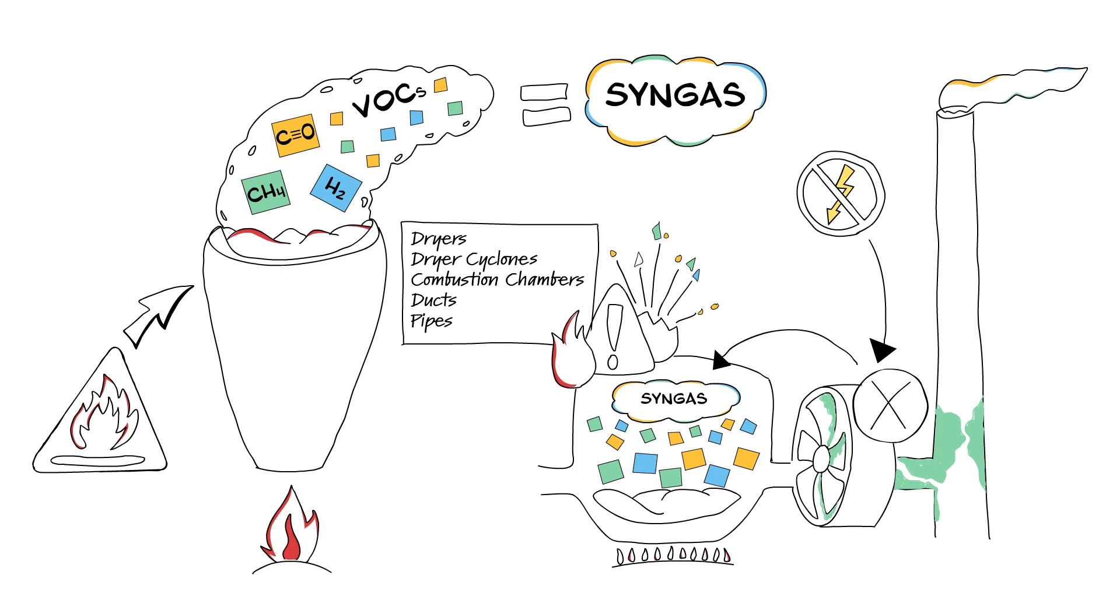Another source of fire in the dryers could be wood fiber itself. If the fiber is dried to the point where there's little remaining moisture and the wood fiber is still exposed to the high-temperature environment, the chemicals within the wood fiber can decompose, forming combustible gas. There is a growing demand for pellets made from other forms of solid biomass, especially from agricultural residues. The same combustible gas risks and safety considerations apply to agricultural residues as for wood.